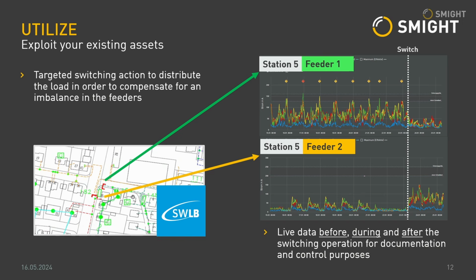We brought this example from one of our customers using our solution at the moment, where in the top right you can see a situation on a feeder where the load was consistently beyond the fuse limit. These little dots on the slide show where that fuse limit was being exceeded. They were then able to make a switching action in their topology which moved that load through to another feeder. This is a perfect situation: you've got existing infrastructure and you're able to use it better and therefore not have to invest. The more insights we can generate to enable utilization, the less money needs to be spent on networks.